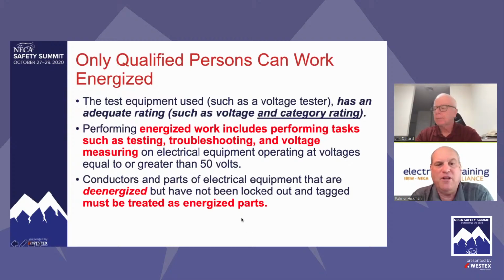Conductors and parts of electrical equipment that are de-energized but have not been locked out and tagged out must be treated as energized parts. So while we know what you mean when you say we only work de-energized, just please, we got to tighten that language up a little bit more. De-energization, as you go through your lockout tagout requirements, and when you go through your achieving electrically safe work condition requirements, it is one step. It is not the same as electrically safe or locked out and tagged out.